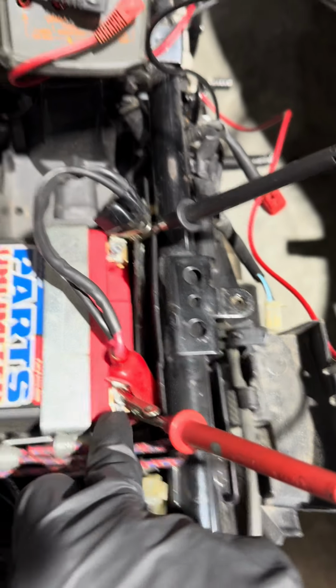So again, it is possible you can be undercharging or overcharging. Both will have the same effect. They will kill your battery. So if you're getting a reading that's not 13.5 to 14.5, somewhere in that ballpark, you've got to start testing your components to see what's wrong. I'm going to set you up a little bit closer here so that I can show you how to do that.